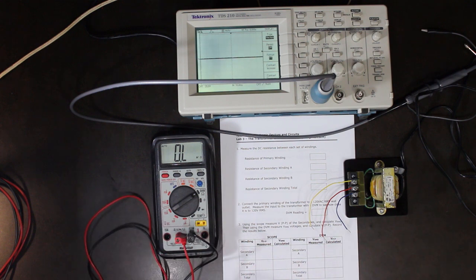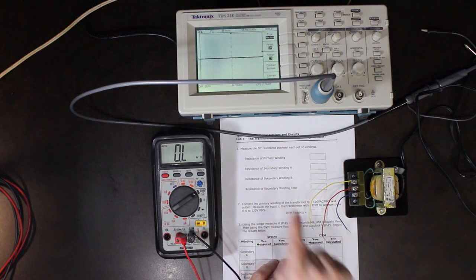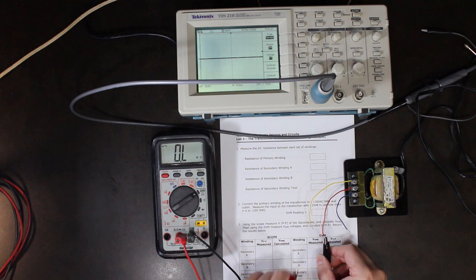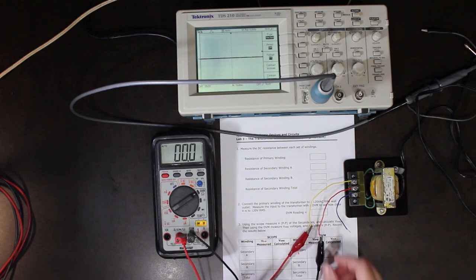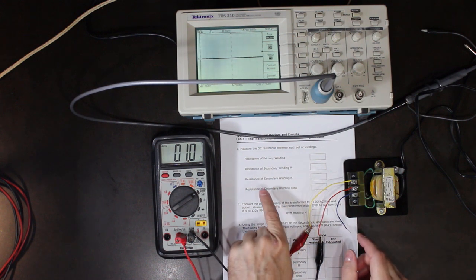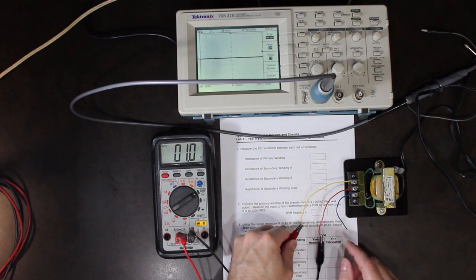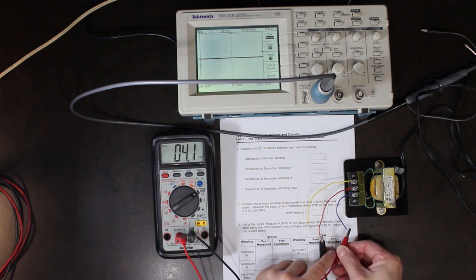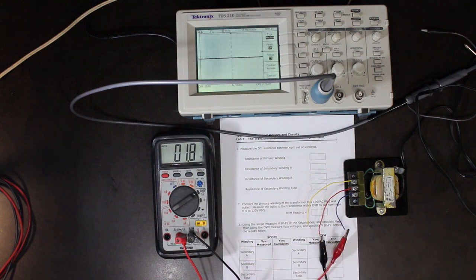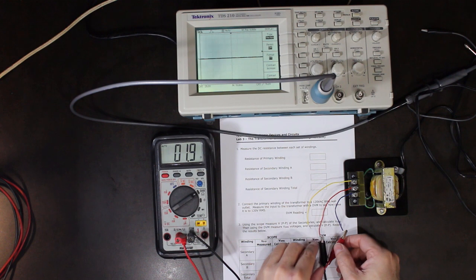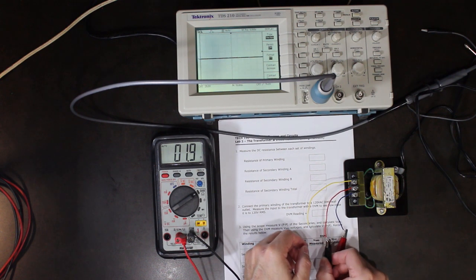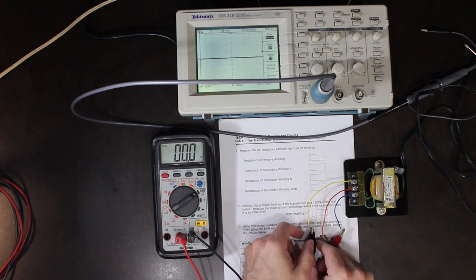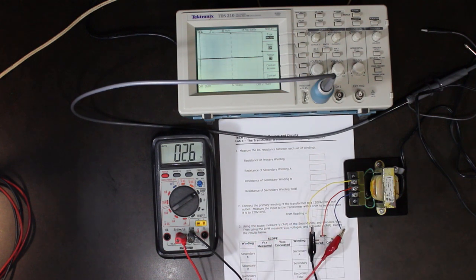Now we're going to look at the resistance of the secondary. Without the transformer plugged in, the resistance of secondary winding A, which we said is red to yellow, and it doesn't make a difference, is 0.1 ohm. Now we're going to go on secondary B, which is red to blue: 0.18, 0.19 ohms. And now we are going to go for the full secondary, yellow to blue, so 0.25, 0.26 ohms.